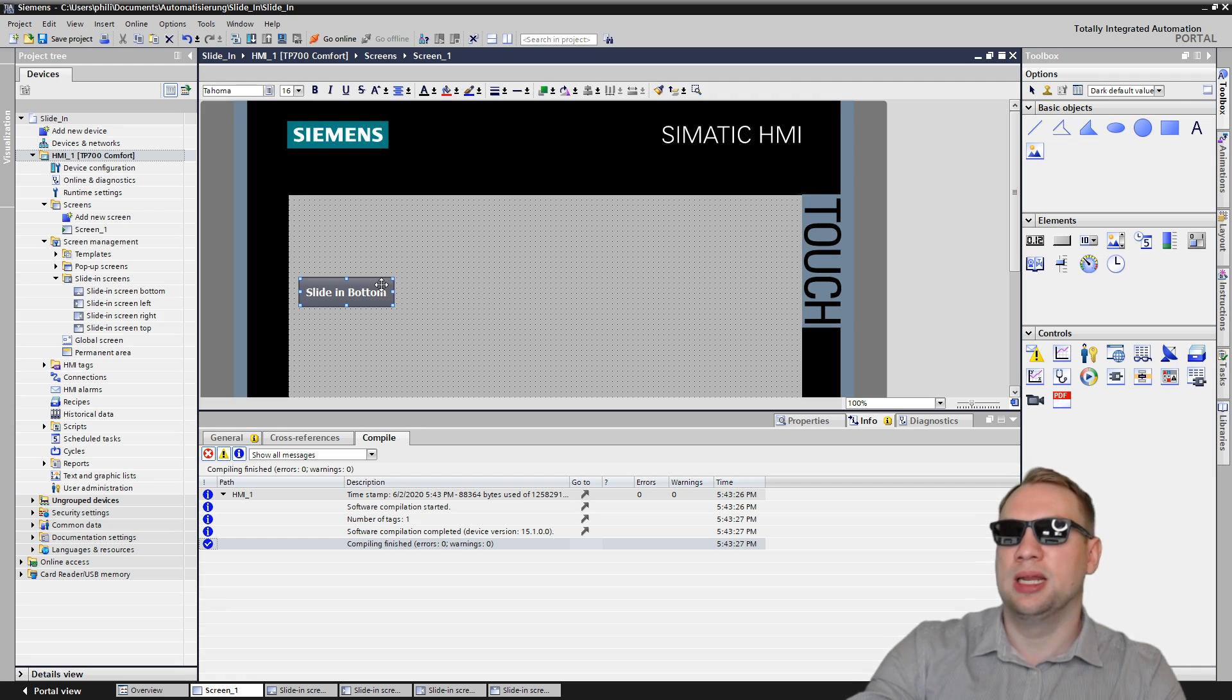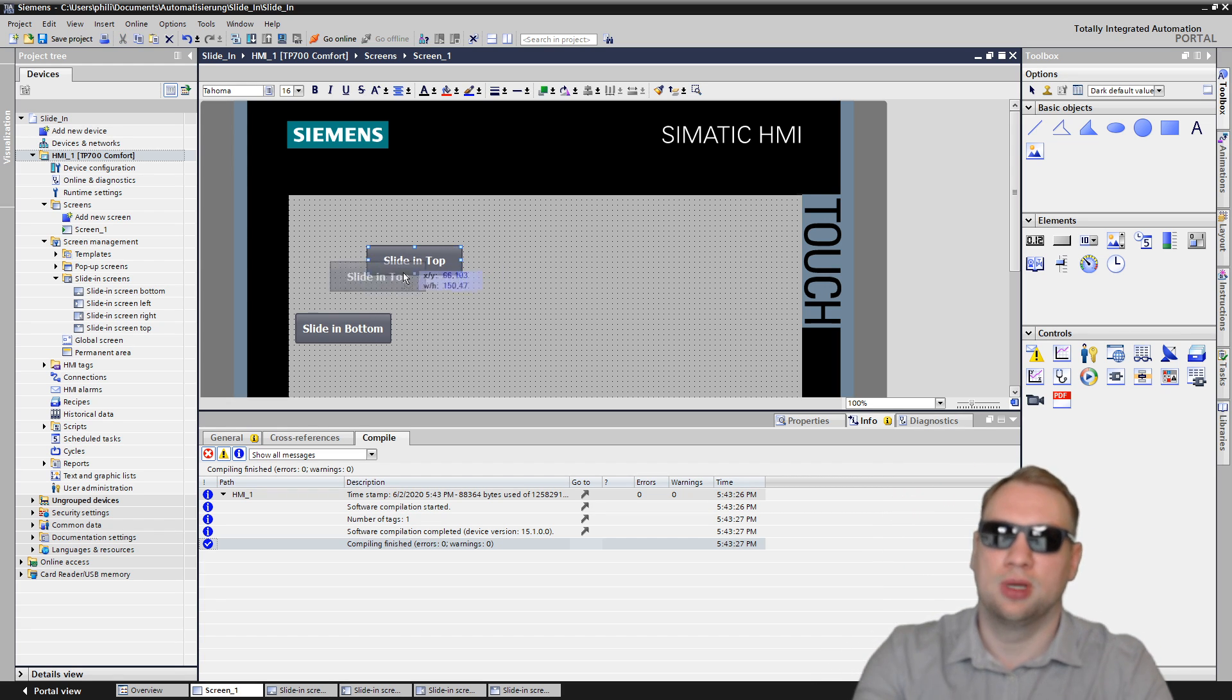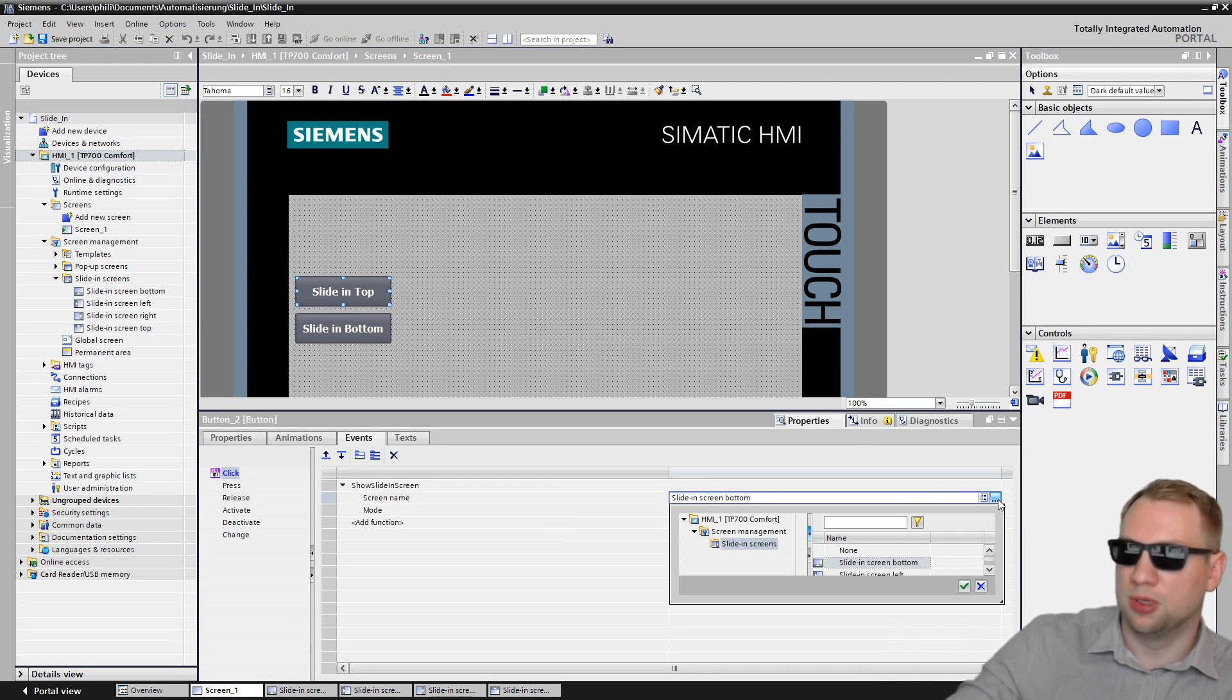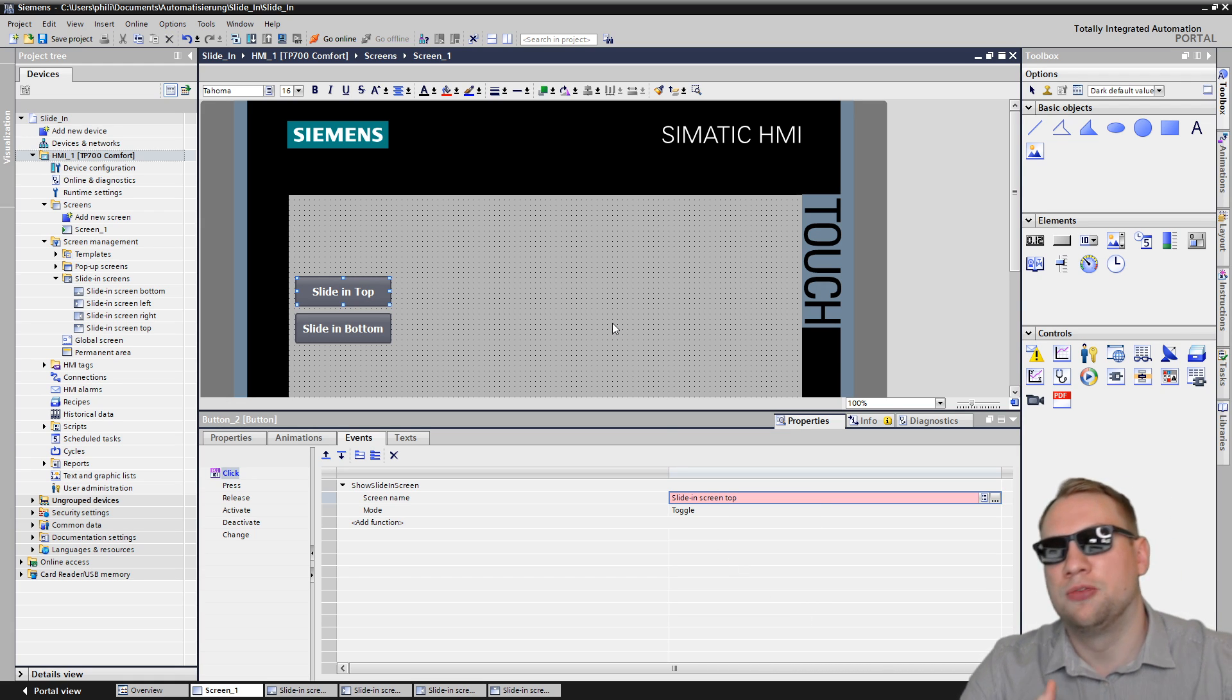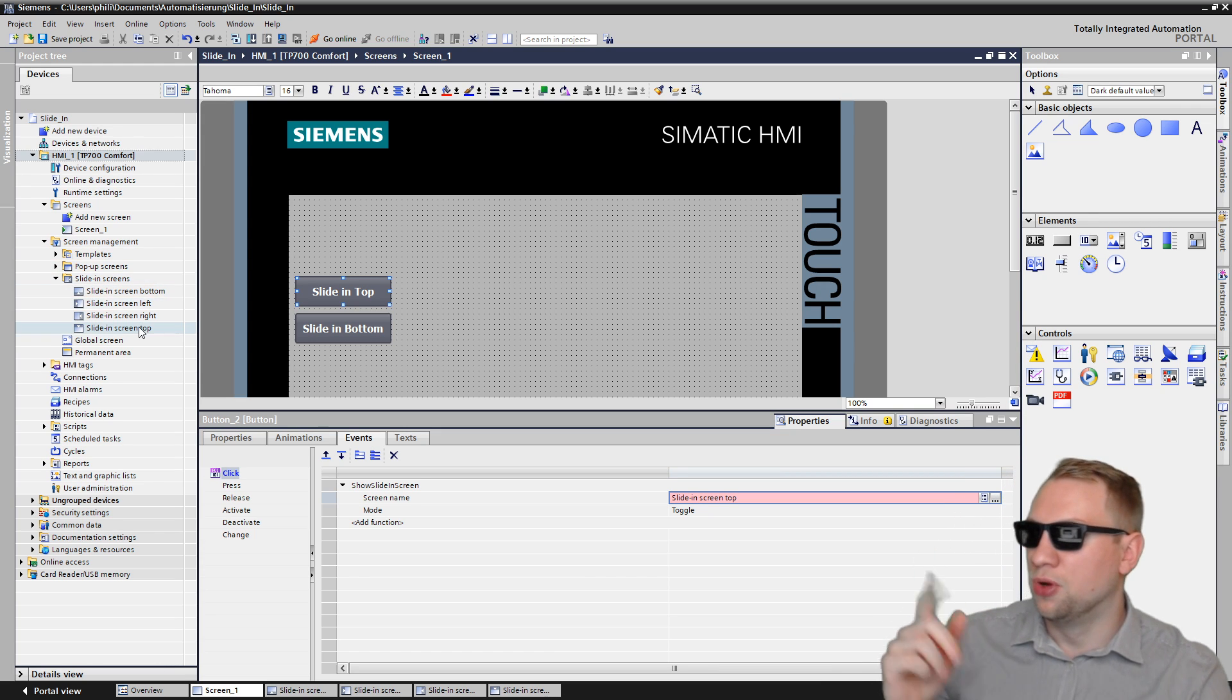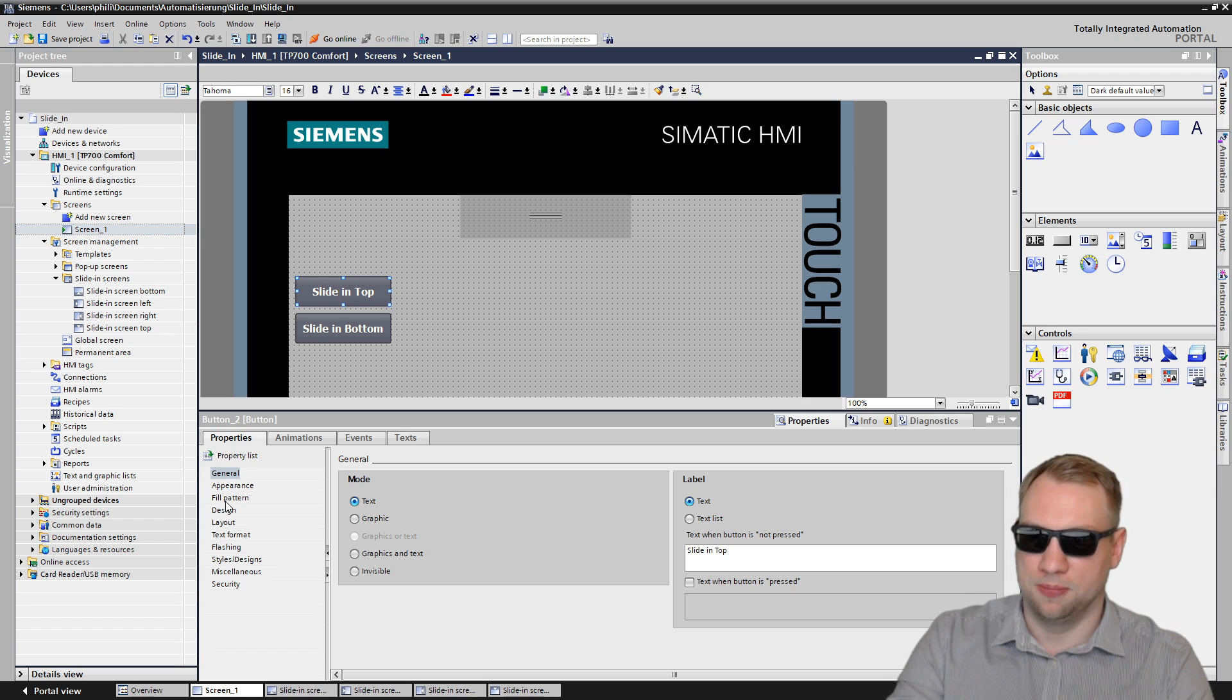Then one last thing that you have to pay attention. If you want, for example, now I want also slide-in top. I want one button for the top, one for the bottom. And now for the top one, I also want to select the top slide-in screen. And it's going to give me an error. It's going to say the specified slide-in screen is not activated. Of course, we cannot use the slide-in screen if we did not enable it. So I have to go to the screen itself, properties, general, and enable it. And now the error is gone.